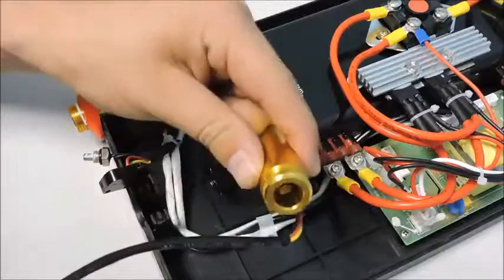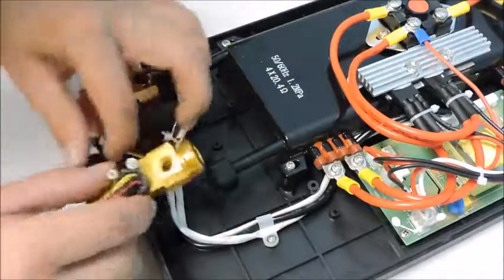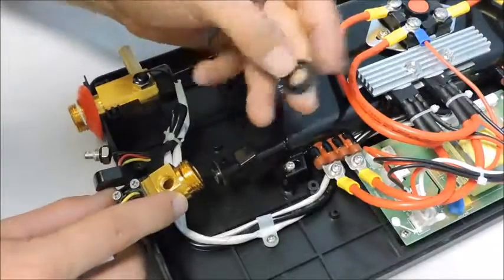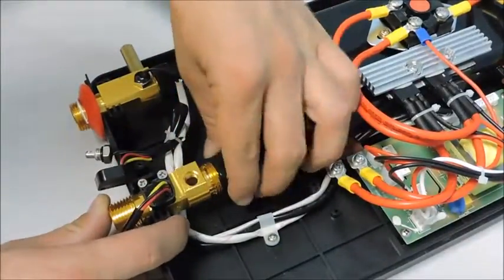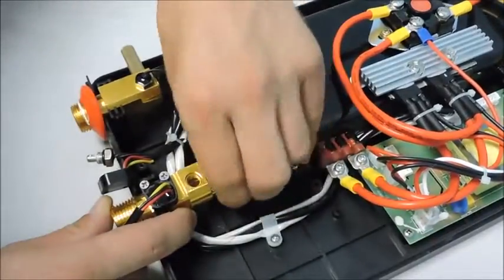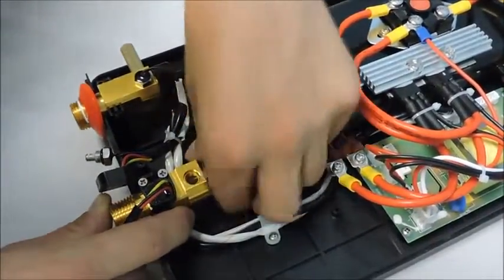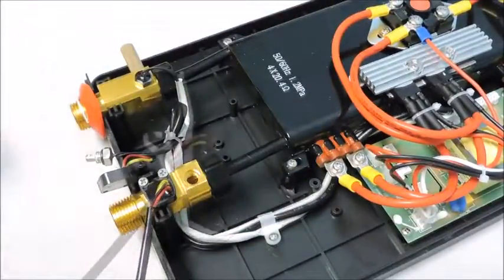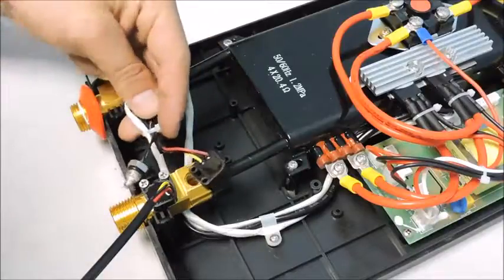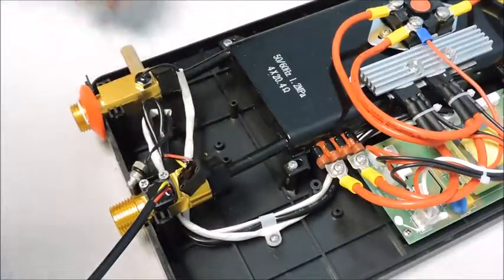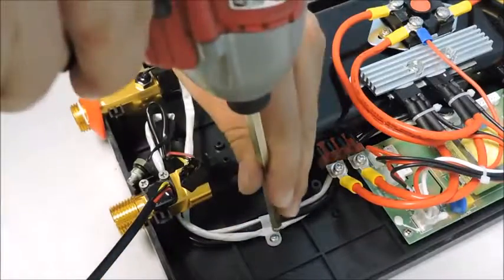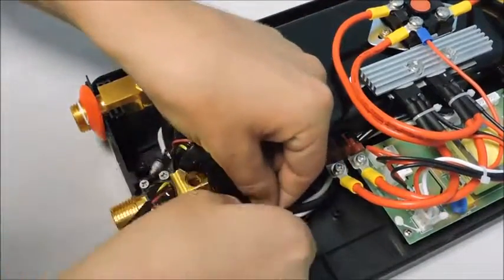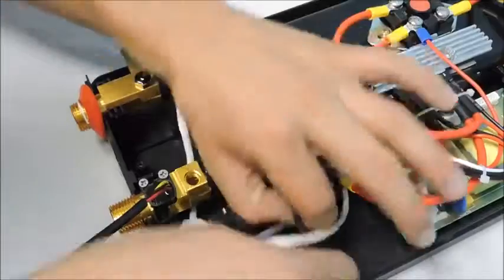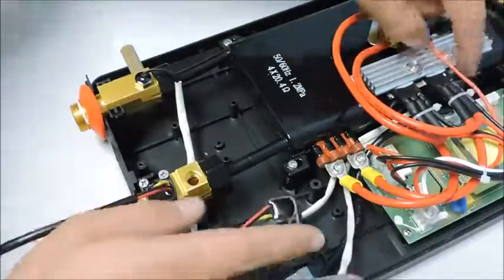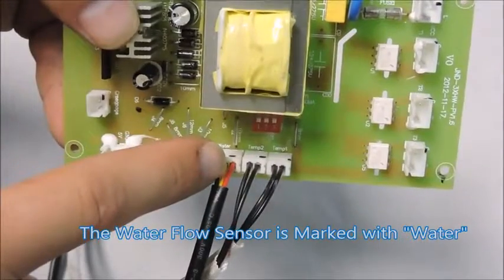Reinstall the new fitting with the supplied water flow sensor attached. Make sure that you did not lose the rubber O-ring that goes in between the fitting and the heat exchange. Secure the fitting to the heat exchange by making sure the connection is tight. Remove the zip tie securing the old flow sensor and also the wire retainer. Next, disconnect the flow sensor from the PCB port labeled water and remove.